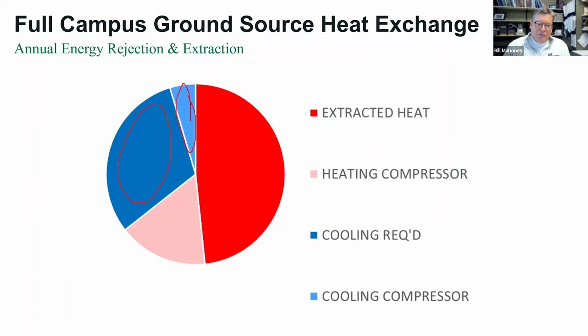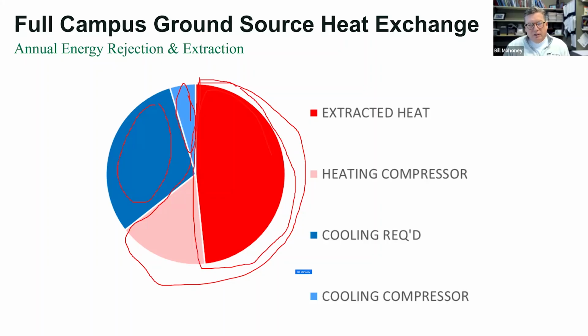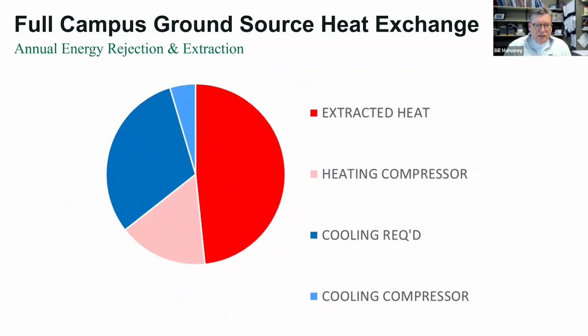And then kind of the opposite way, in the winter, I might have a load that's this whole 2/3 of this pie, but I only need to get this portion out of the pie, out of the ground, because this portion, the light one here, is the compressor energy that we're going to put into our heat recovery chiller. And so that also gets used as beneficial heat. So this is a balanced system, which is the point of this slide. The load on the building cooling on an annual basis does not have to equal the annual energy load of heating. It's just got to be close, but you make up the difference with these compressor energies that help you in the summer and in the winter because of the direction the heat's flowing. If that makes sense. Next slide.